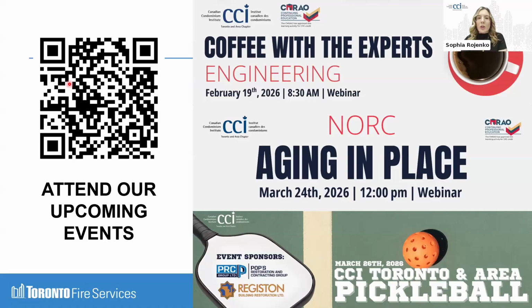Okay, some more questions on the same note. What about existing buildings? I have a building less than 2 years old, but I do not believe that the lobby furniture is fire retardant. Do we have to replace it? In residential care occupancy, the answer is yes, you have to replace it. Or you comply with one of the other requirements, like it's sprinkled with smoke detection, which is a very high bar. But if you're going to fall under the approved provision, yes, you need rated furniture if you don't have sprinklers.